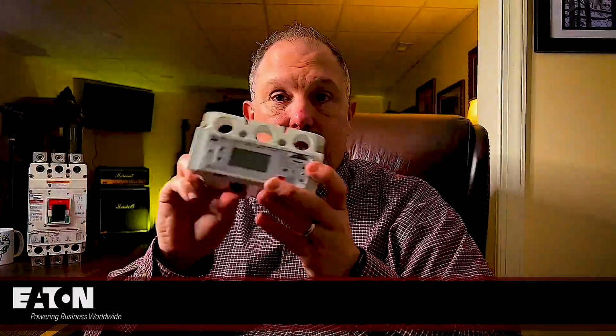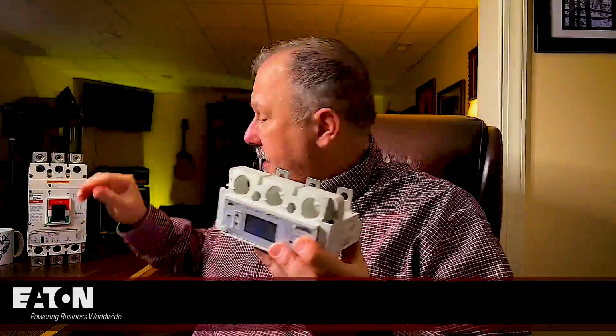So an electronic trip unit is something like this. This is what you would find down here on the bottom of this circuit breaker. This device, and you got to put it the right way. It's not this way, it's that way. Sits right here. Okay, that is an electronic trip unit. That would be something that you could put on a breaker like this. So this is a PXR25 trip unit.